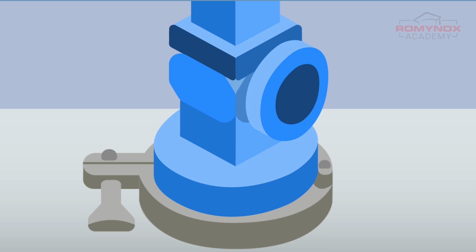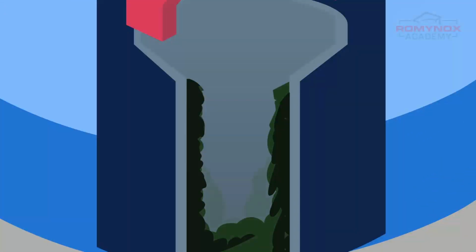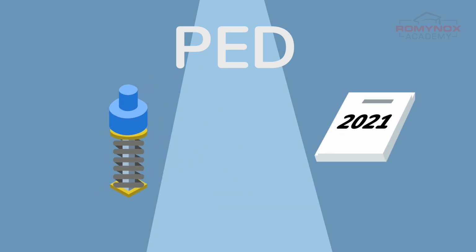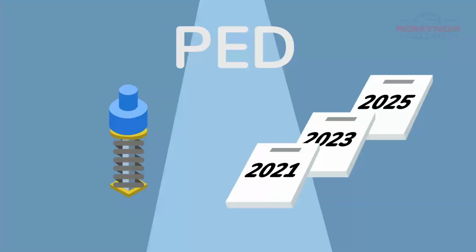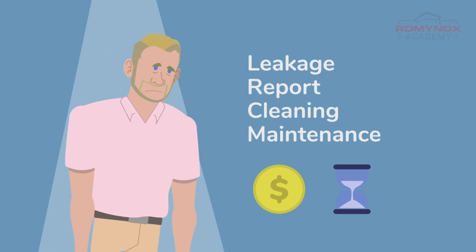Even systems fitted with proximity switches will not detect every activation, so the risk of insidious leaks remains. Another problem is that safety valves can be difficult to clean. Standard models have mounting depths that far exceed the cleaning standard limits, and this can lead to contamination. According to the PED, a safety valve must be readjusted on a regular basis, at least every 2 years, and after each activation. This takes time, money, and downtime for the system.